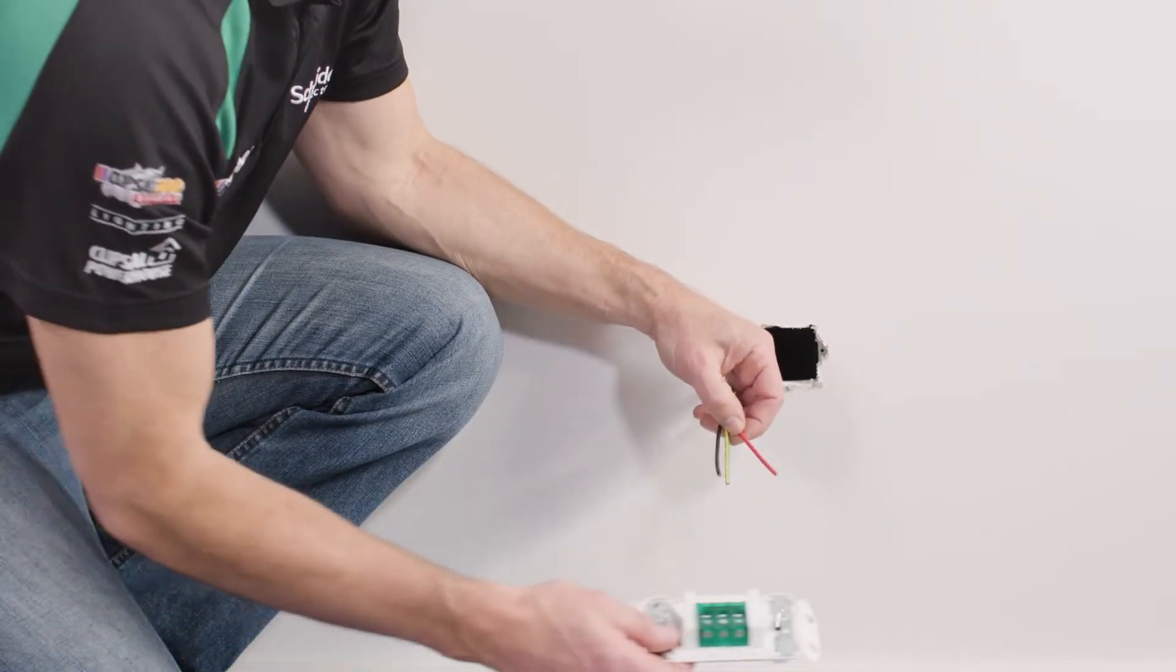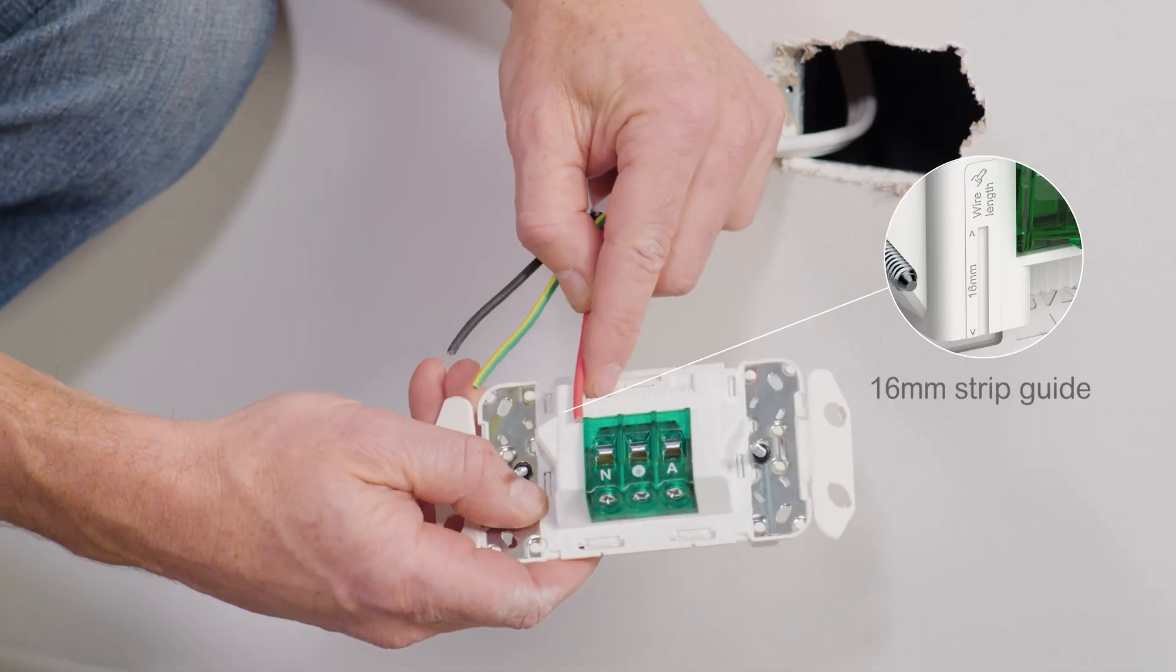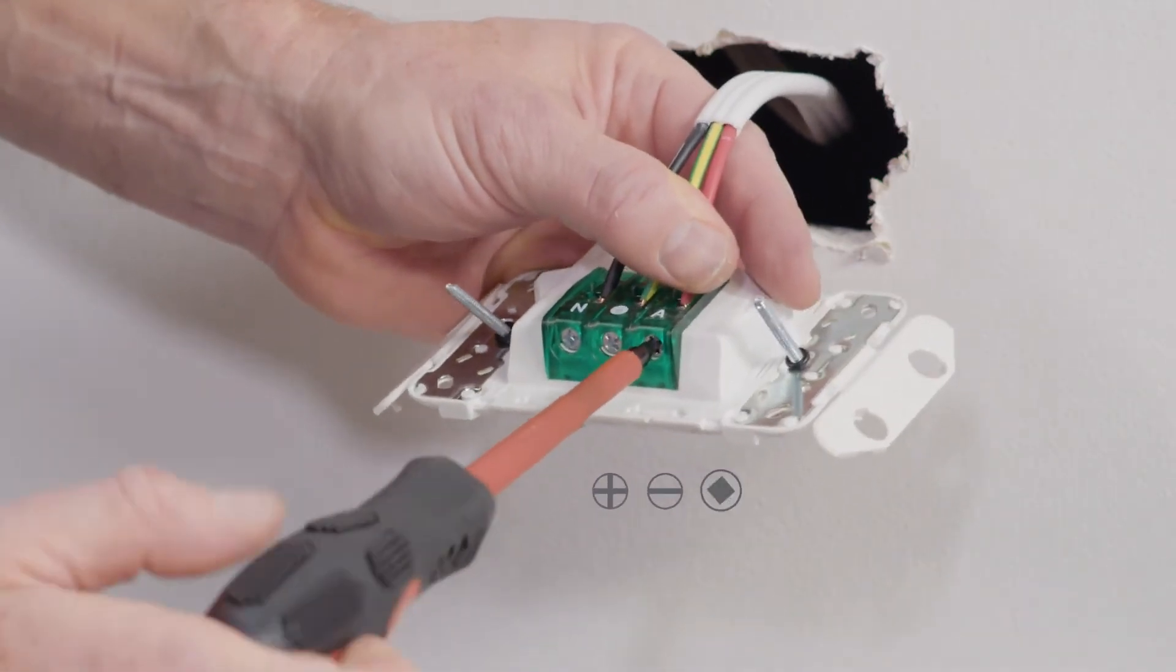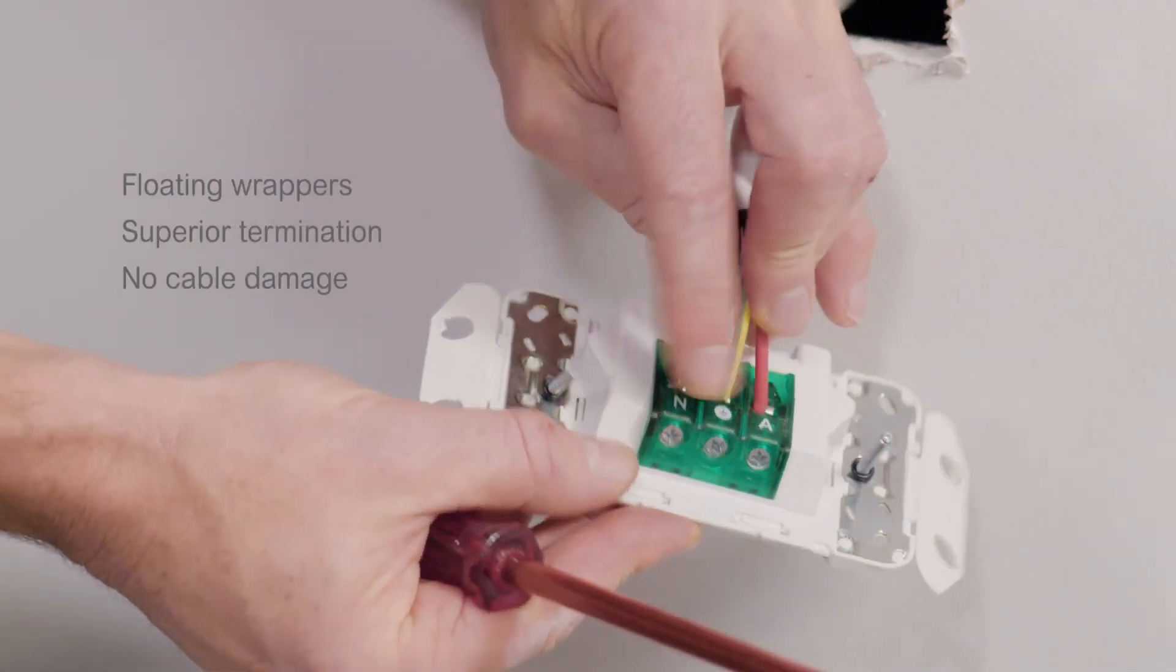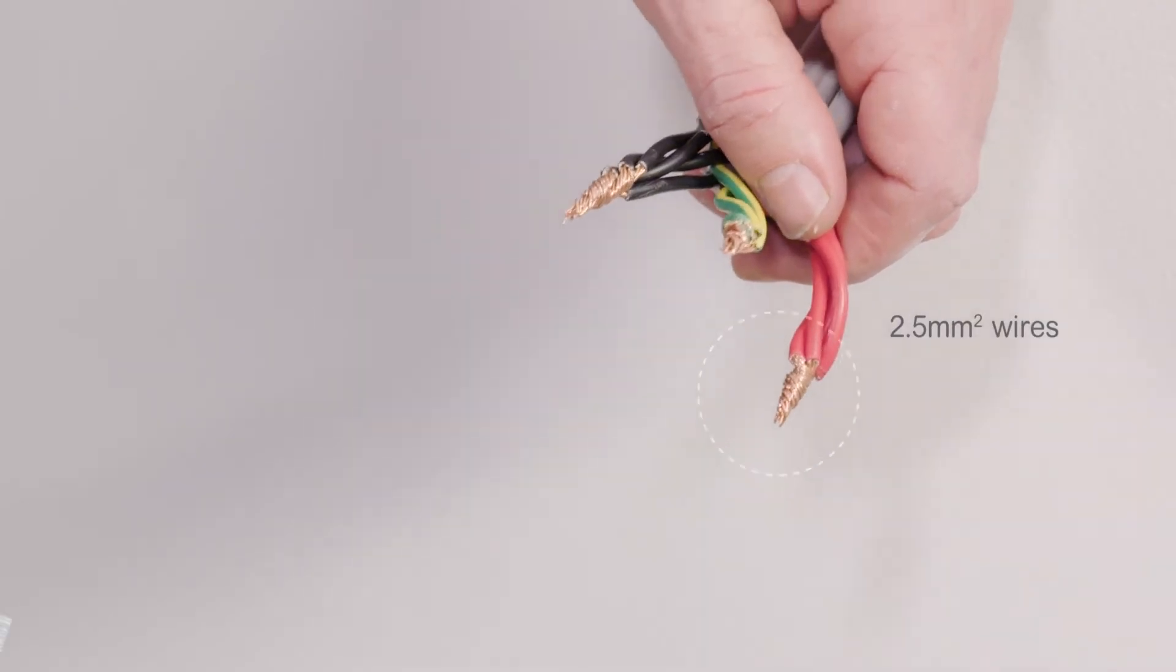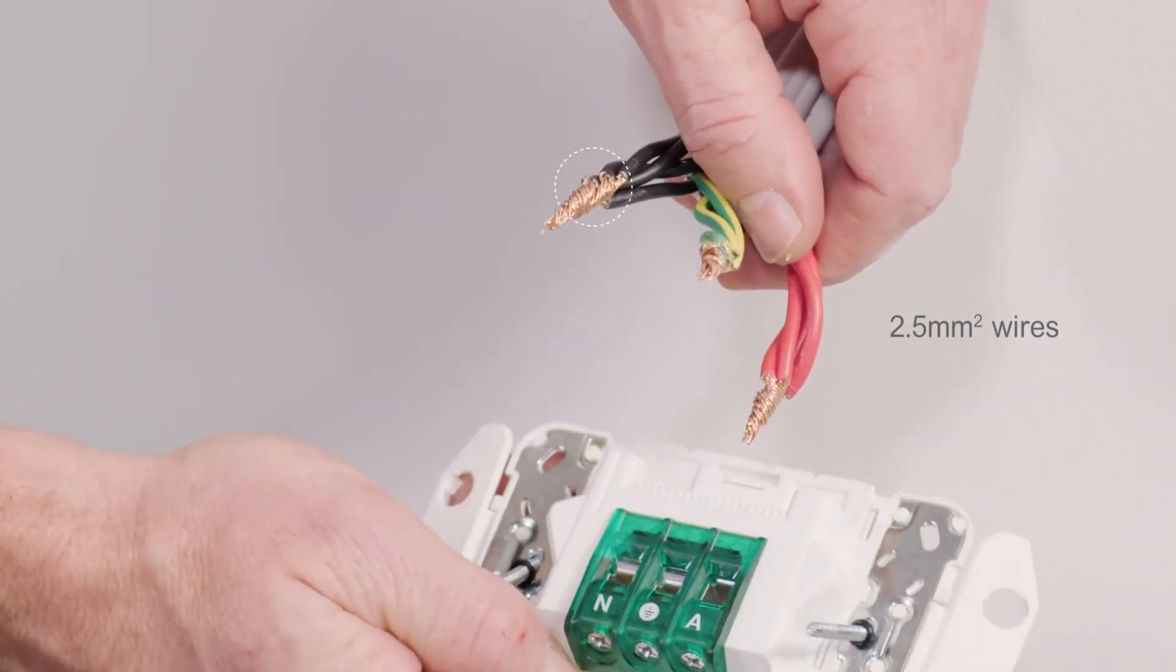Fitting off sockets is simple. Just check your strip length, and use a Phillips, flathead, or square drive. You can even use a battery drill. Floating wrappers offer superior termination, and the terminals take up to four 2.5mm wires.